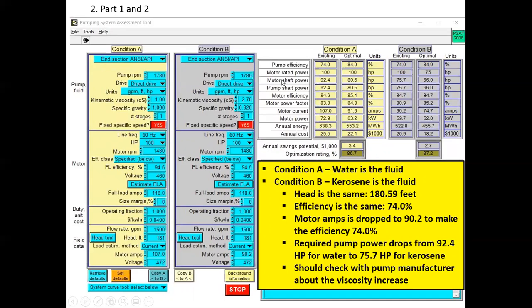Now there is one thing I guess could happen here, that the motor actually could speed up a little, because the motor power is going to drop from 92.4 to 75.7. That's pretty far down in the weeds. You could project that a little bit, and then you would have to plot up the pump curve, system curve, and see that might give you a very small increase in fluid flow. But within the basic assumptions of using this given data, I wouldn't expect anybody. I didn't go to the trouble to do that. I wouldn't expect you to either.